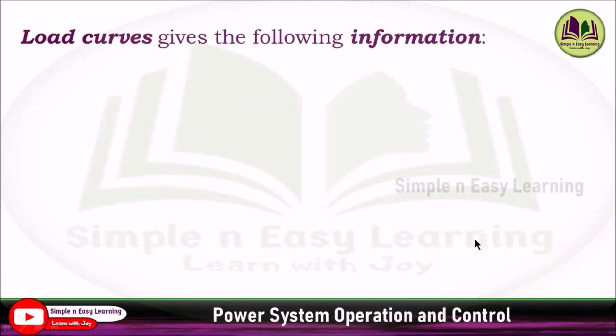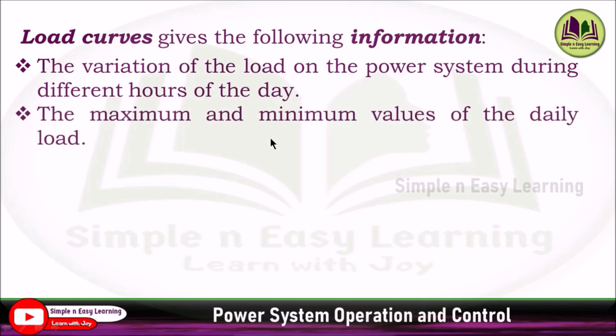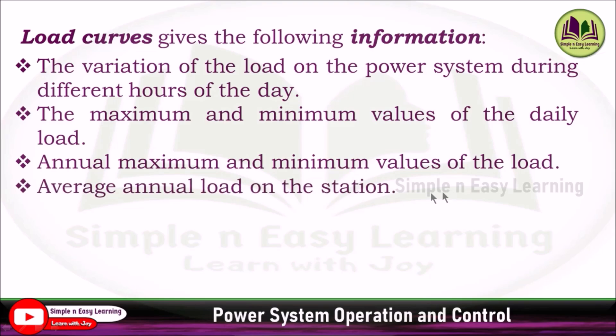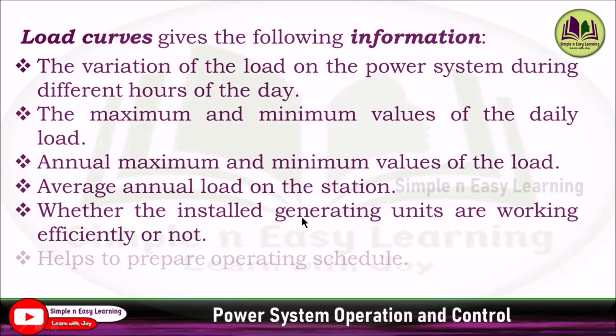The load curve gives the following information: the variation of load on the power system during different hours of a day; the maximum and minimum values of daily load and annual maximum and minimum values of the load; the average annual load on the station; and whether the installed generating units are working efficiently or not. This load curve also helps to prepare the operating schedule in an economic manner — based on the load demand, we can shut down some units and implement economic load scheduling.